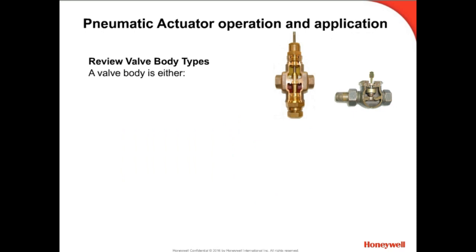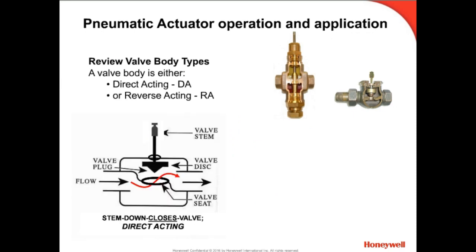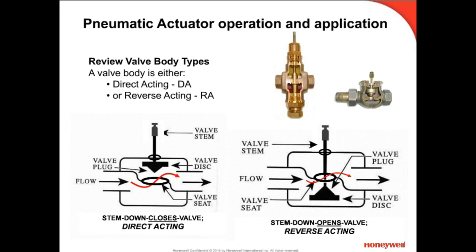Valves are available in several configurations of normally open and normally closed design. It has all to do with the relationship between the actuator and the valve body. Two-way valve bodies are either direct acting or reverse acting. A direct acting valve body closes to flow as the stem is pushed down — this design may also be called a stem-down-closes type of valve. Conversely, a reverse acting valve body opens to flow as the stem is pushed down — this design may also be called a stem-down-opens type of valve. Note there is no return spring in these diagrams, so there is no normally open or normally closed discussion possible at this point.